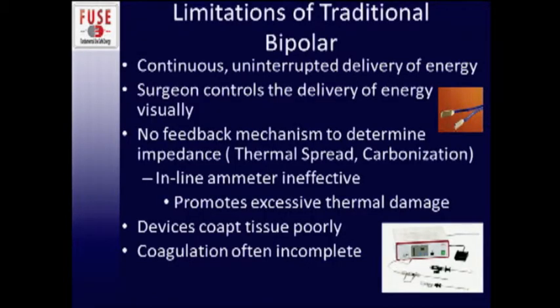Traditional bipolar energy is overall safer than monopolar but does have its limitations. It provides continuous uninterrupted delivery of energy, but the surgeon controls delivery using only visual cues — we look at thermal spread, which by the time we see it is probably too much, and carbonization, which leads to sticking. People have put inline ammeters to let surgeons judge coagulation level, but these have been proven ineffective in studies and were shown to promote excessive thermal damage. These devices overall tend to coapt tissue poorly, making coagulation often incomplete.